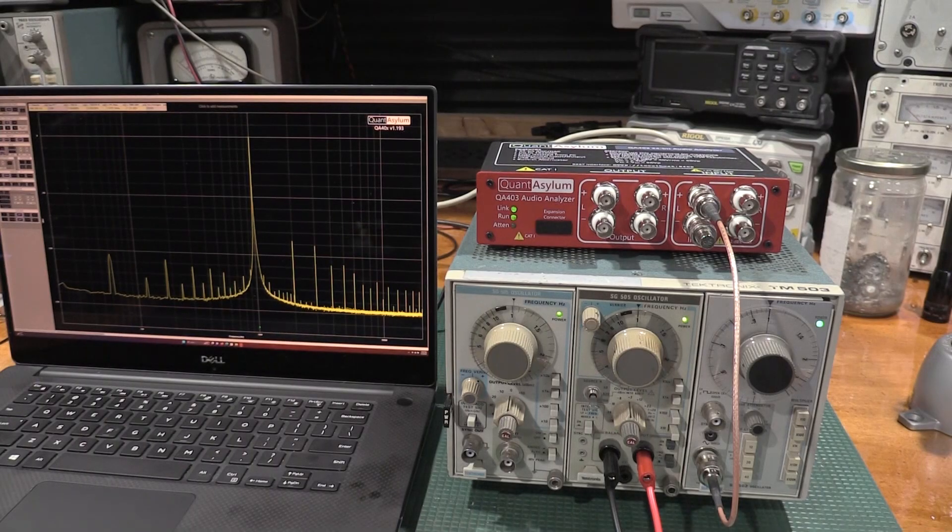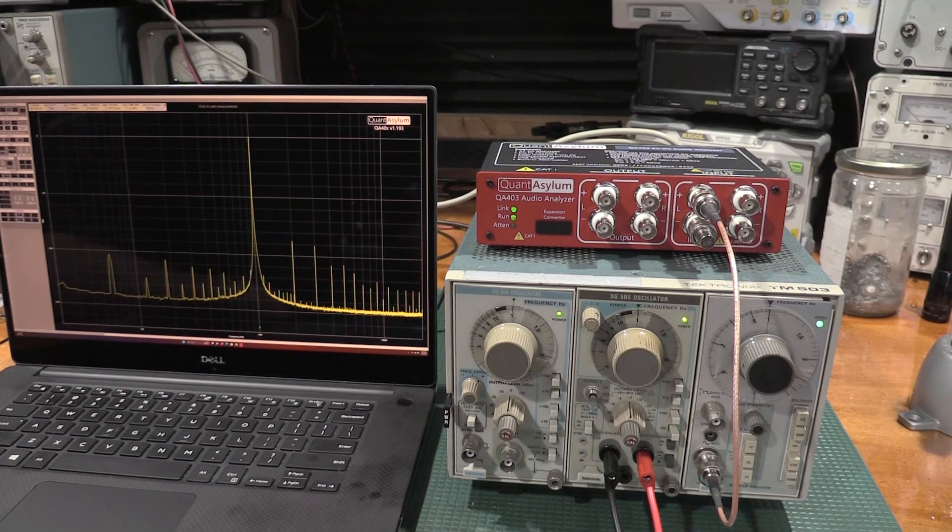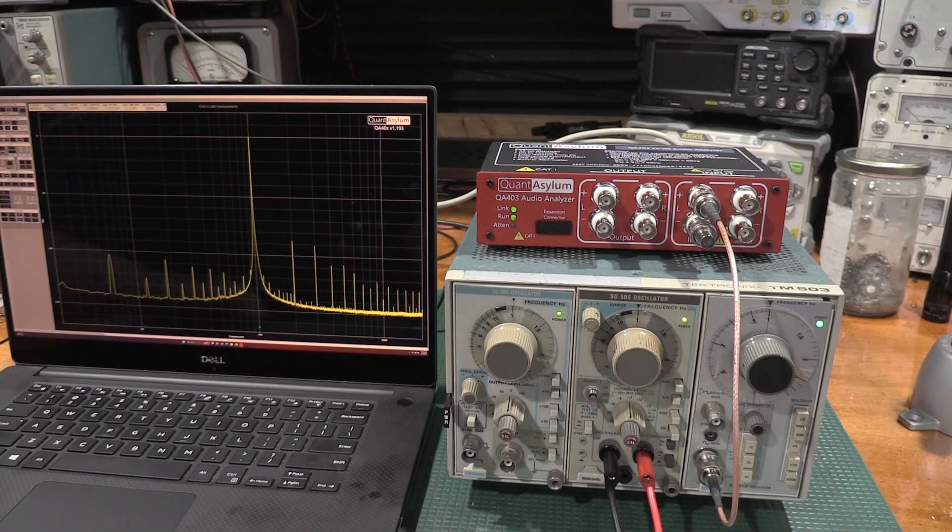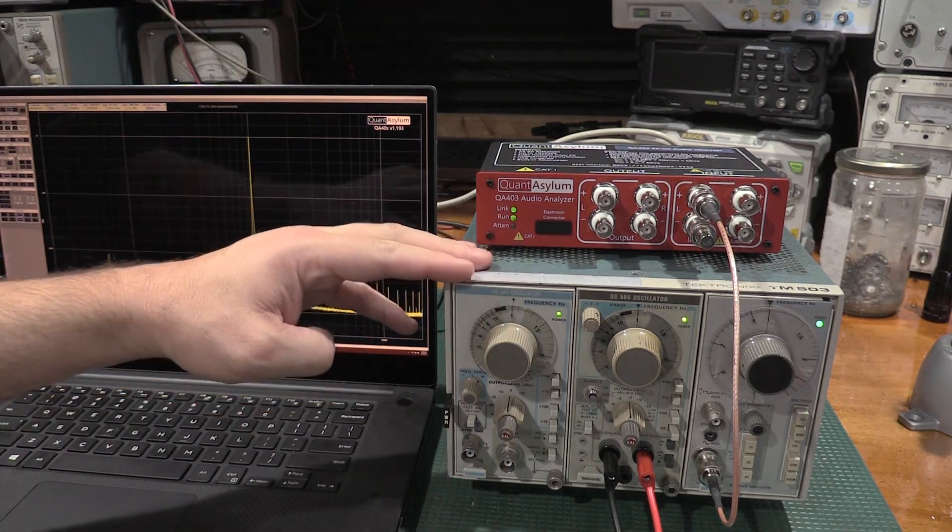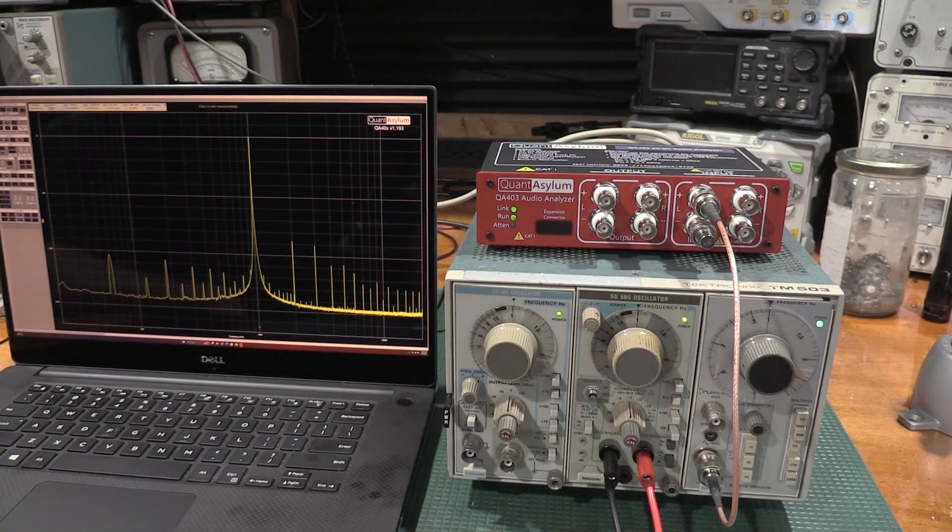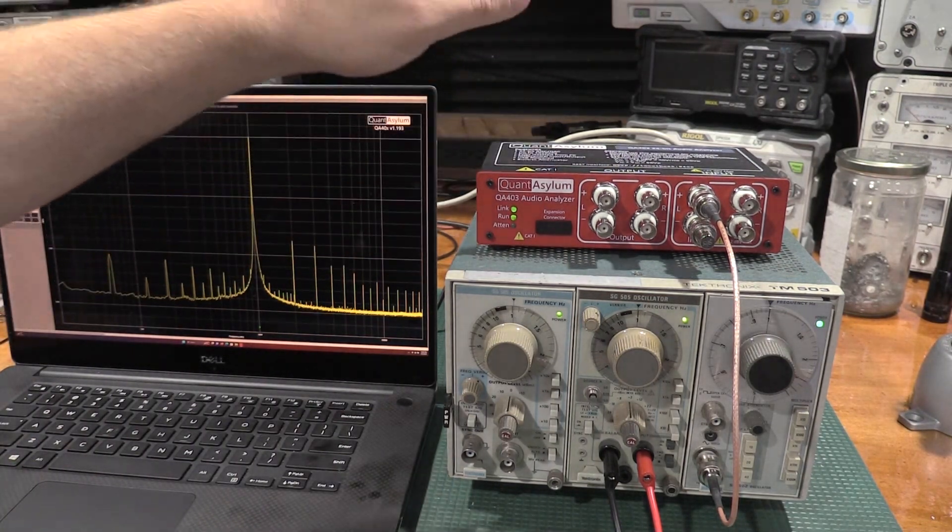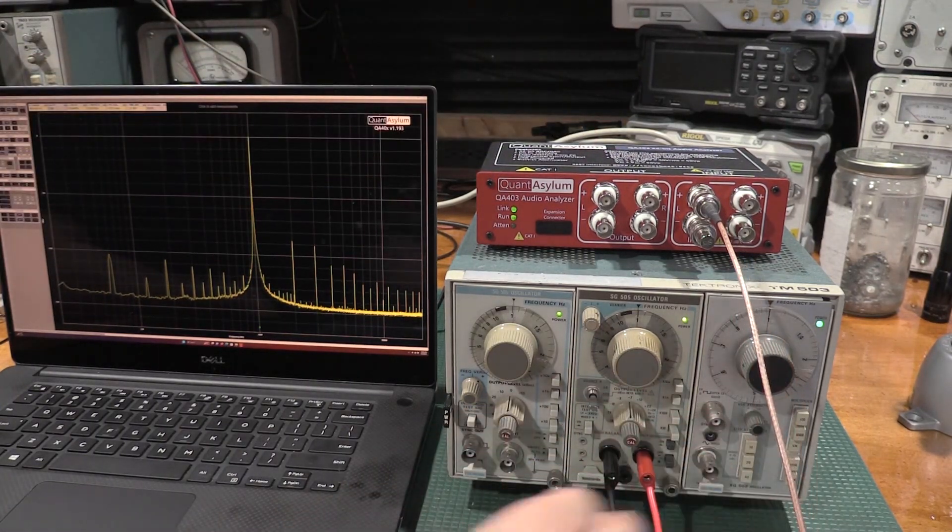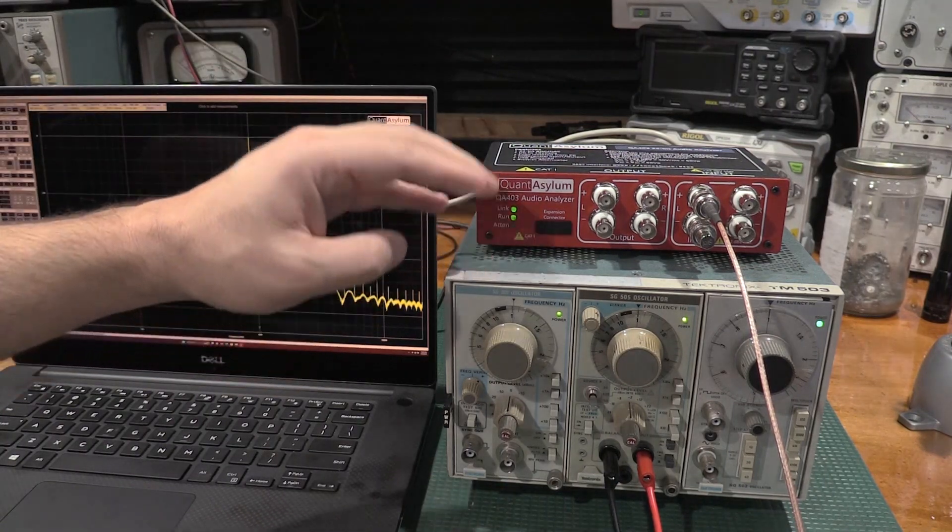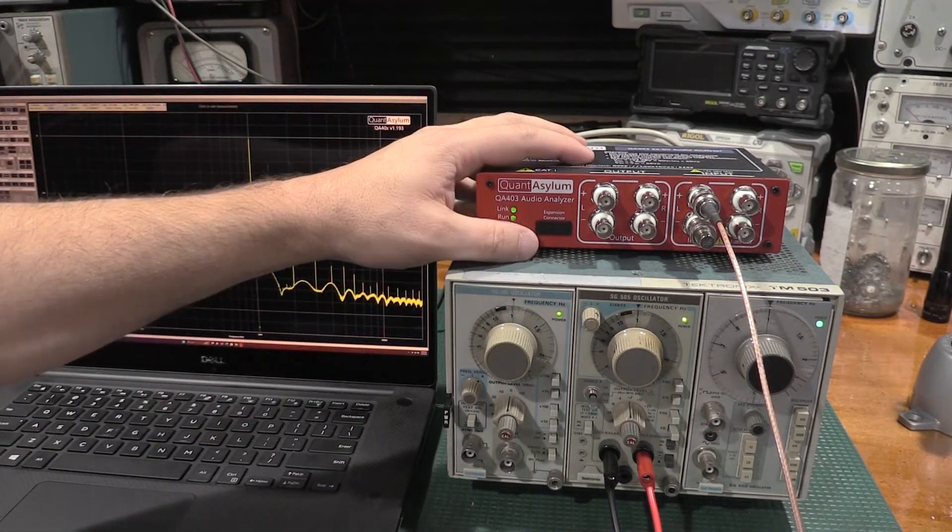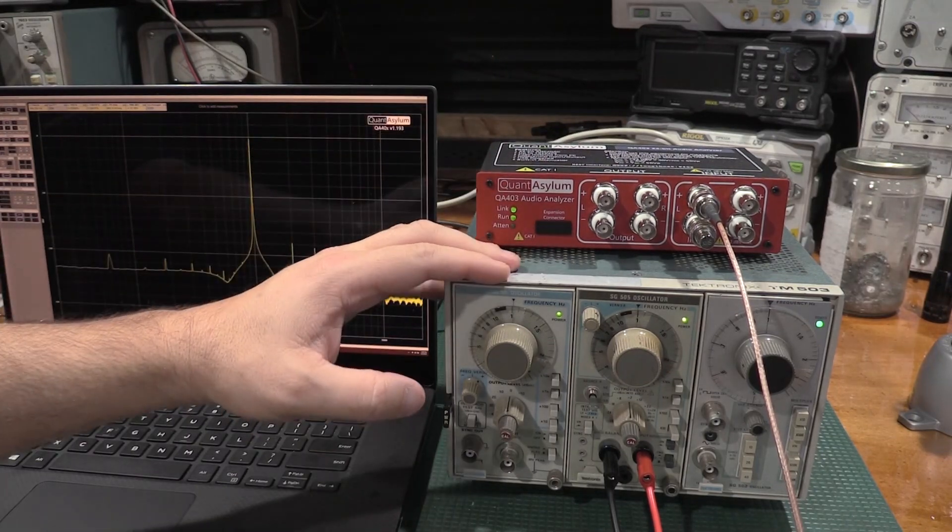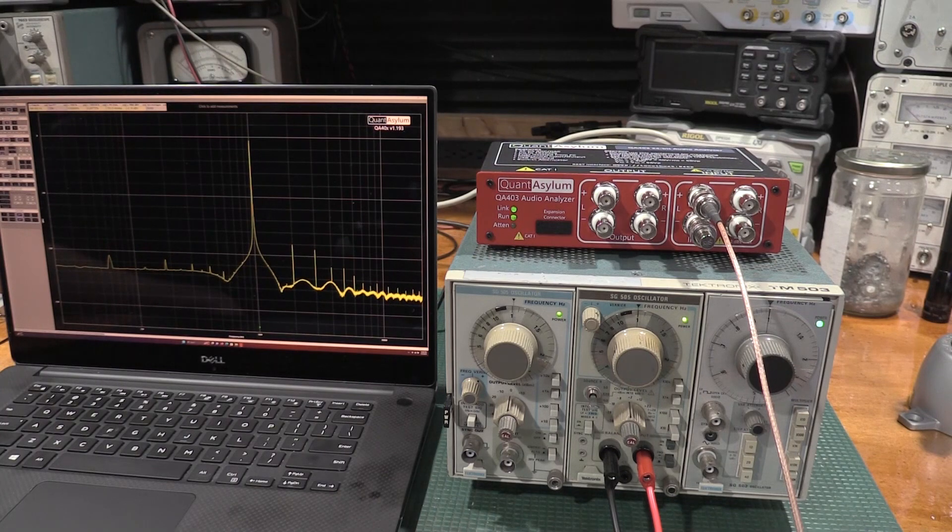Some oscillators that were made in the 80s and 90s measured by an instrument that was made yesterday. Especially doing the THD measurements in the SG505s is a real pain in the butt. If I had known about this a while ago, I would have been able to save some money looking around for the calibration fixture, which is the notch filters and everything like that to do the 505s. But being able to measure it raw, much easier than going through the tedious process of dialing out an SG505.